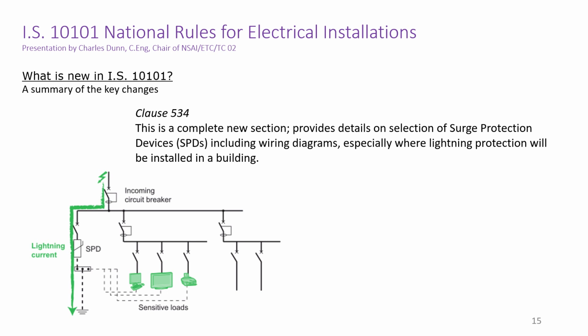But there are instances of overvoltages on the power network which can affect delicate electronic equipment. That's your flat screen television, your computer, your Wi-Fi unit. There is now so much electronic equipment connected in all buildings that surge protection is well recommended for every electrical installation. Clause 534 has wiring diagrams to cover nearly every installation, so it's worth a look as there is good guidance there.